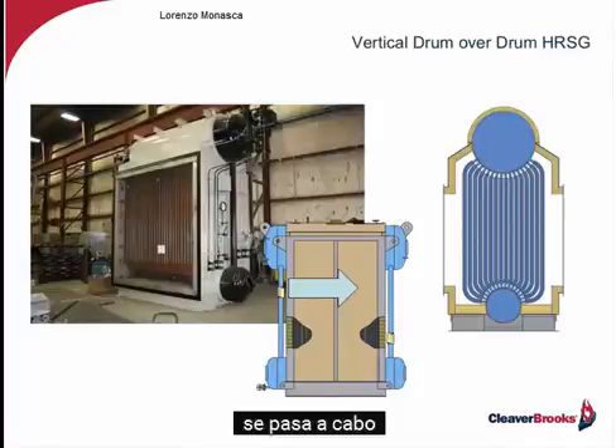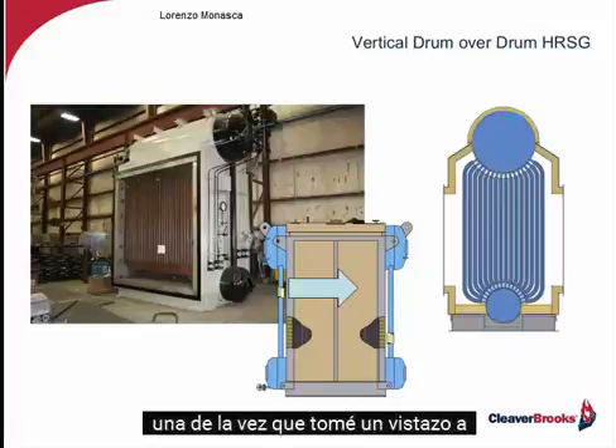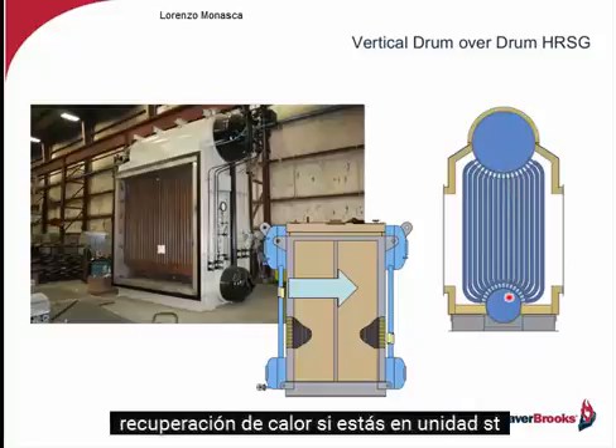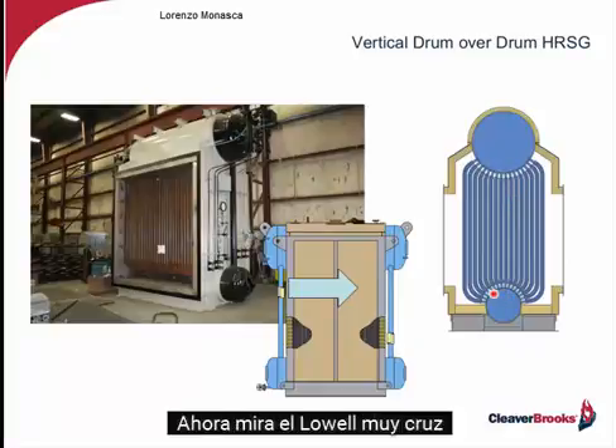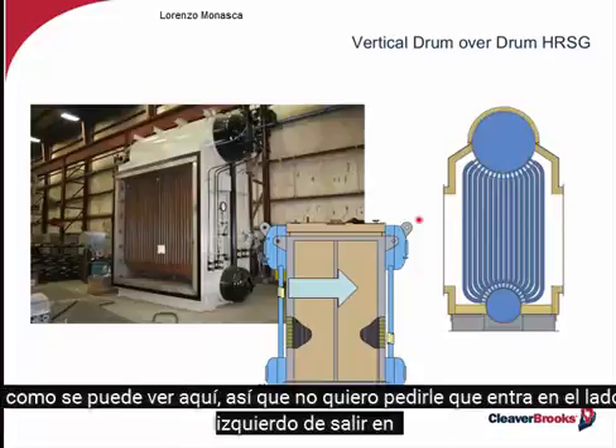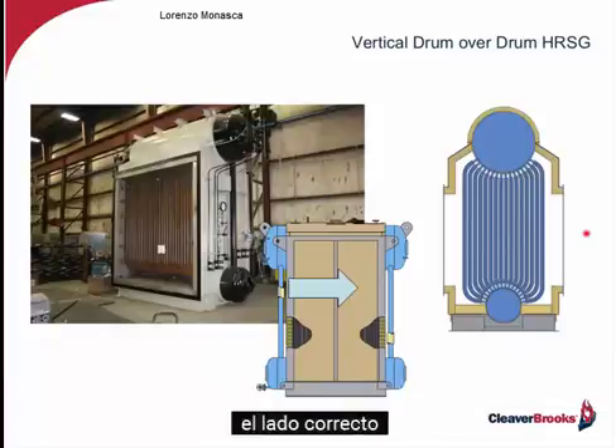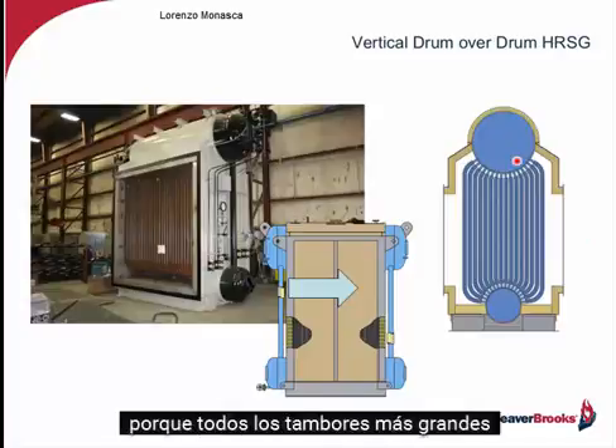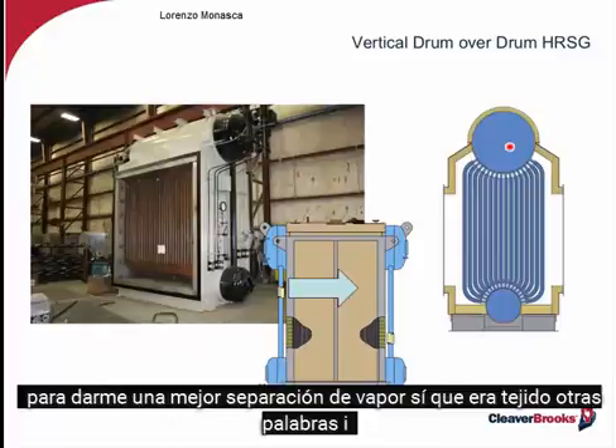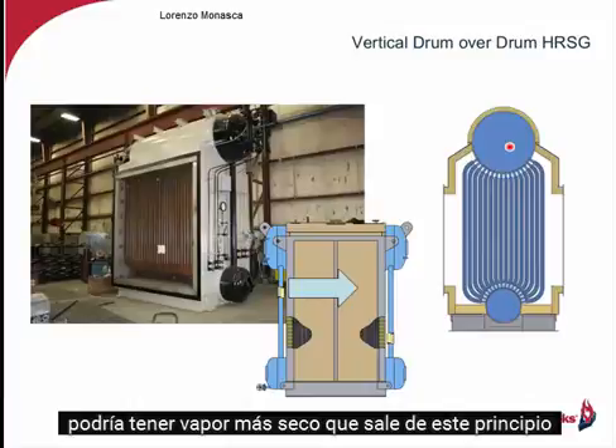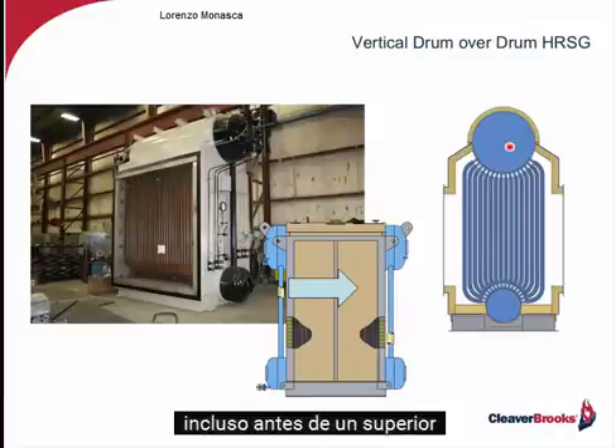Now, what I could have done, if headroom was not a problem, one of the things I might have looked at was a drum-over-drum heat recovery HRSG unit. It could be cross-flow, as you see here, so I've got one pass coming in on the left side, exiting on the right side. It's a small footprint. Because of the larger drums, it would give me better separation of steam, if that was an issue. In other words, I might have drier steam coming out of this initially, even before a superheater.